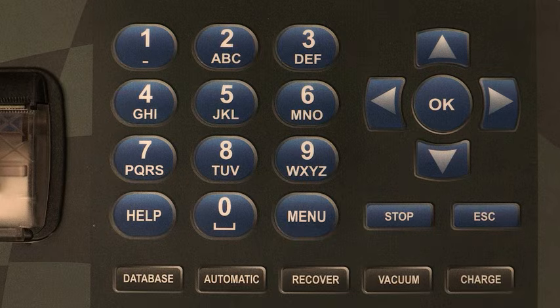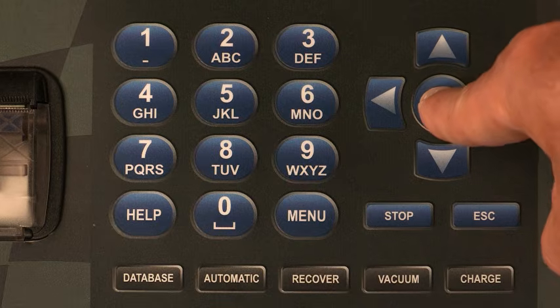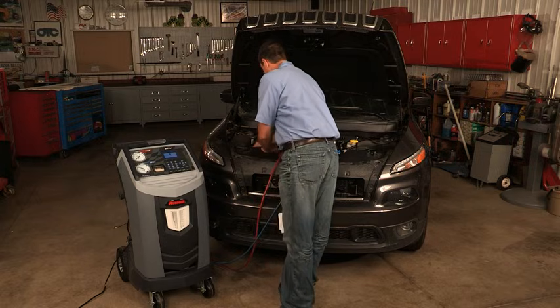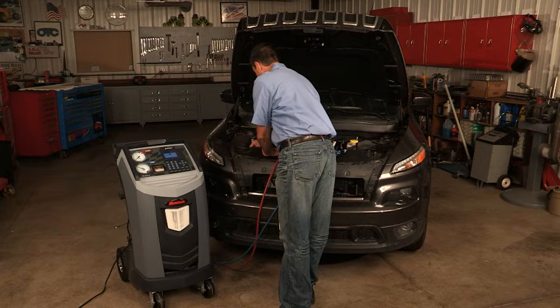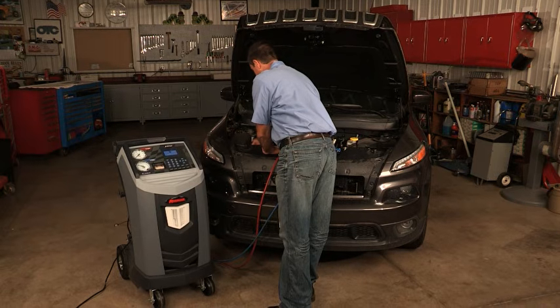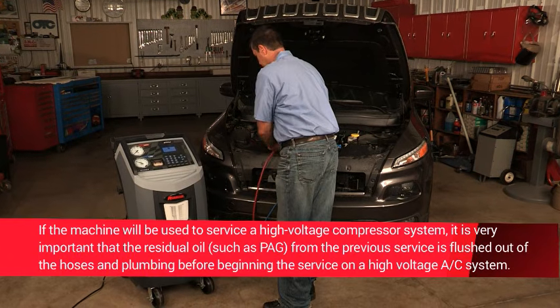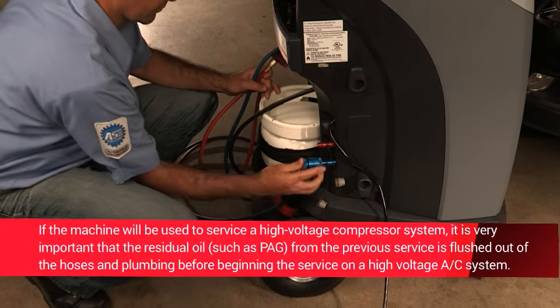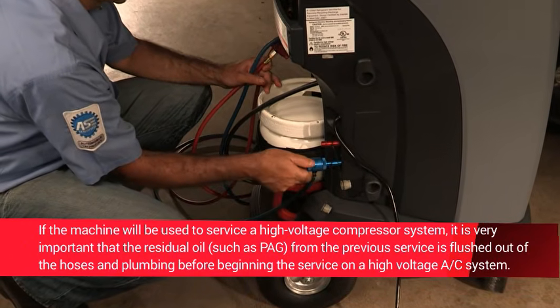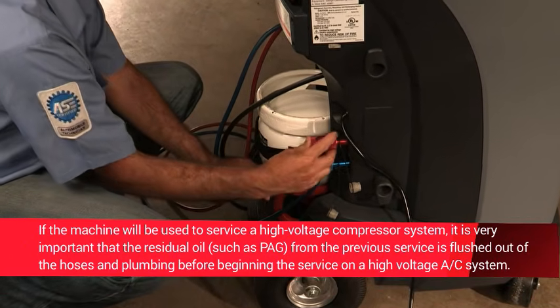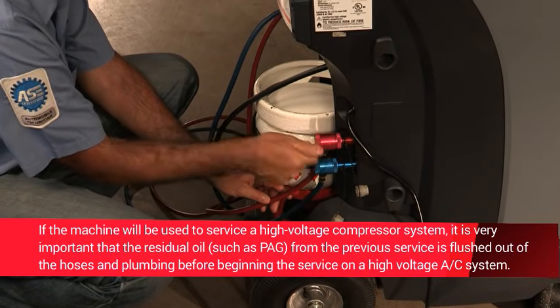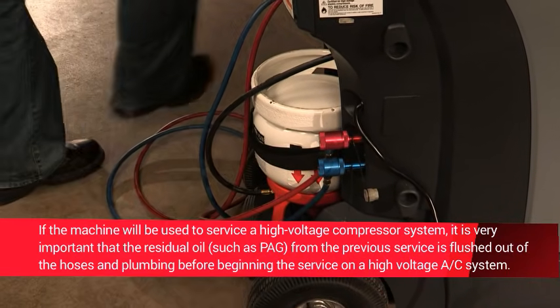At the end of the charge, the machine prompts to do a diagnostic pressures test. Select OK to begin clearing the hoses. This prepares the machine for the next service. In order to do a manual charge procedure, first connect the service hoses to the machine's service ports and open the couplers.